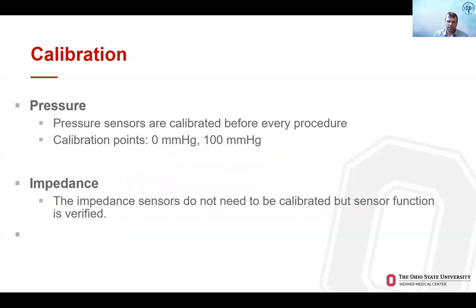Probes need to be calibrated before every procedure. You have to zero the pressures and make sure the pressure sensors are calibrated properly so that pressure readings are accurate. The impedance sensors don't need to be calibrated, but their function should be verified before the test.